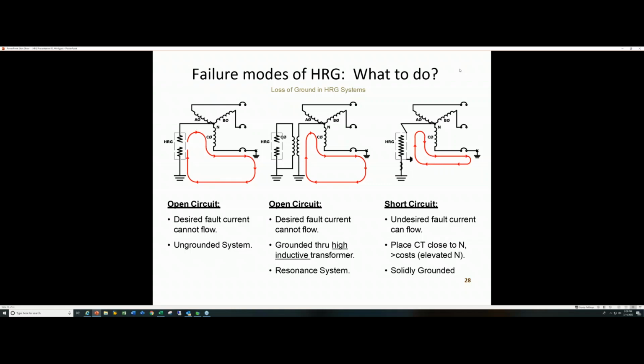So failure modes, HRGs, what do we do? All right, over here, there's a drawing of an open circuit, right? The middle is an open circuit, and the right-hand side is the HRG in service there with a short circuit. So if you weren't maintaining the resistor, what would happen? Well, you'd have an open circuit. You'd have an ungrounded system. So basically, when you have a fault on this phase, right, you have an ungrounded system. You have nowhere to go. And you guys know the issues with an ungrounded system when something like that happens and the potential risk it puts people at.